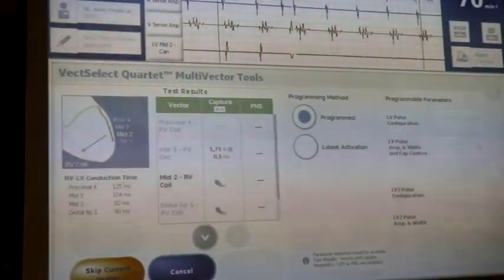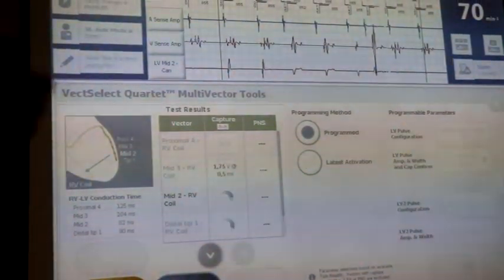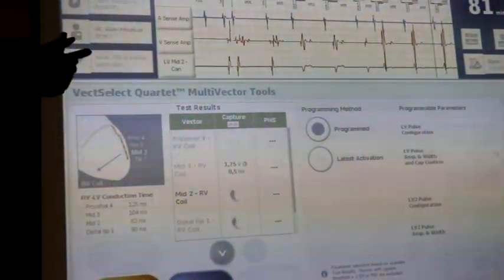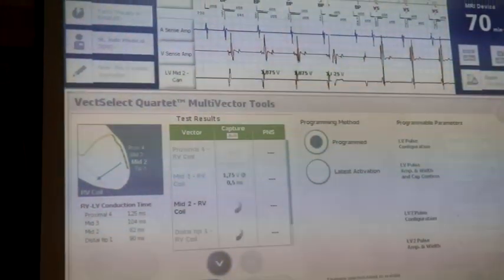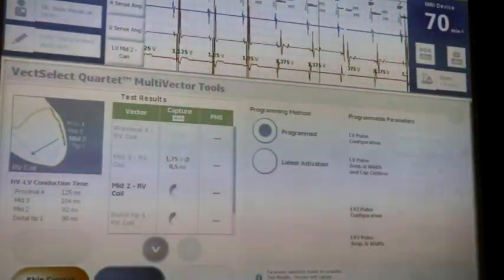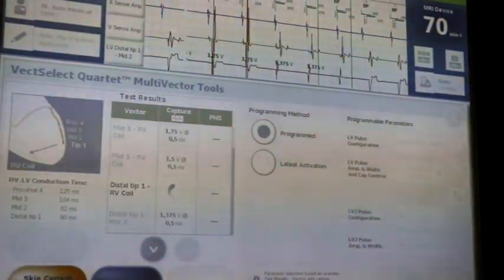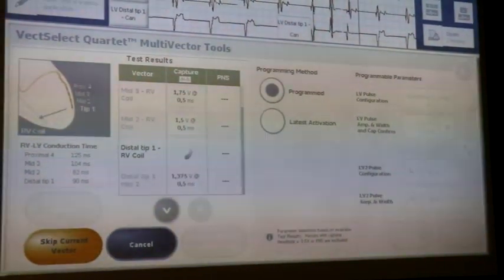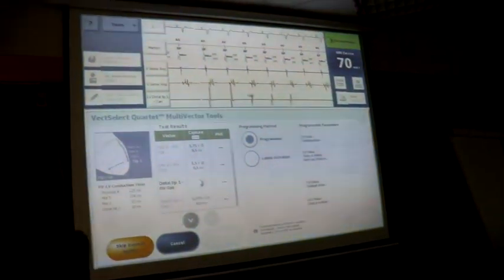So I've seen people totally exclude the whole left ventricular lead for phrenic nerve, along the whole LV lead, which is unusual anatomically, but it was because every circuit they tested had 2 in it. So they were 1 to 2, phrenic nerve, 2 to 4, phrenic nerve, 3 to 2, phrenic nerve, 4 to 2, phrenic nerve. And they were like, this lead's capturing every electrode. I was like, okay, it's just on 2. Yeah, they were like, oh. Fortunately, they didn't operate. We just programmed it off 2 and it's all fine. So the phrenic nerve was just at 2.